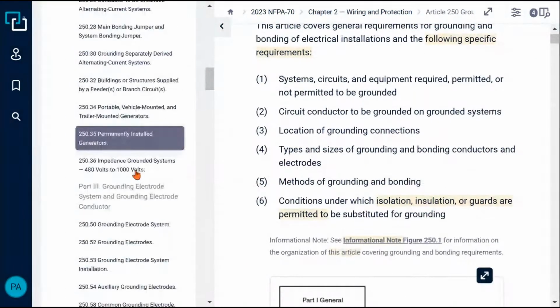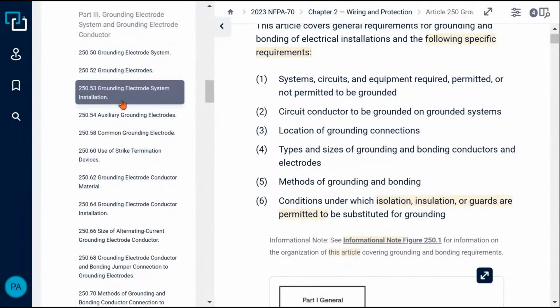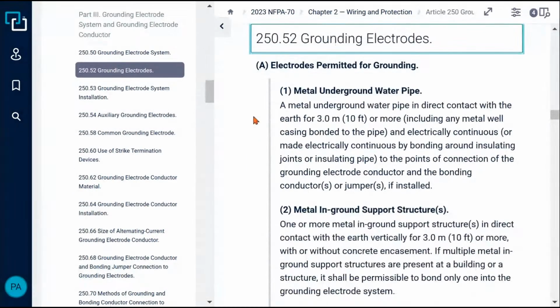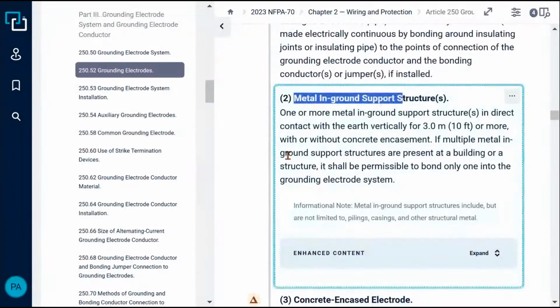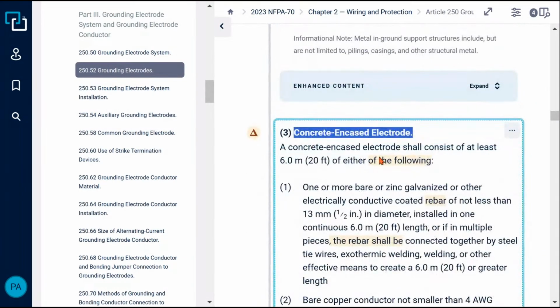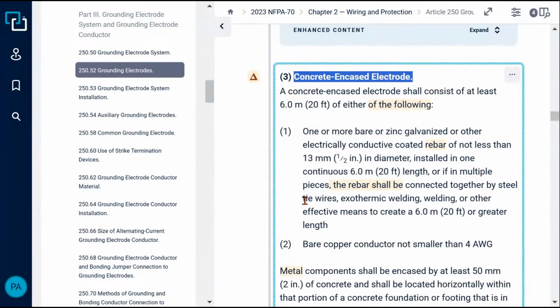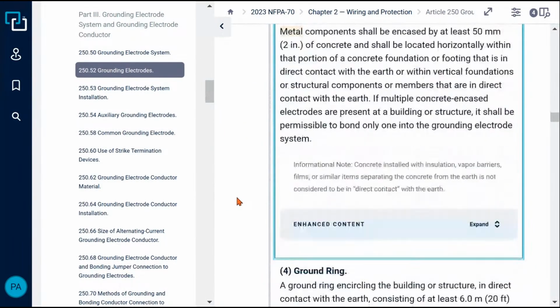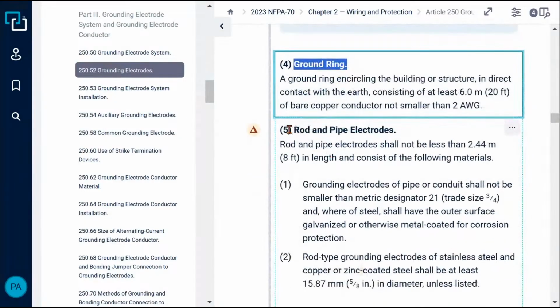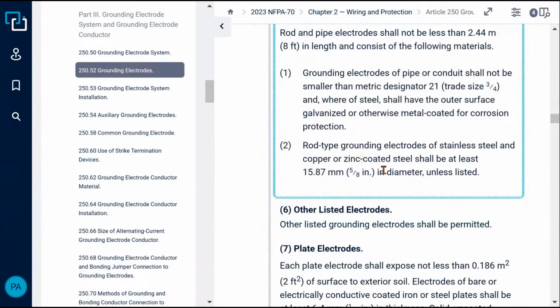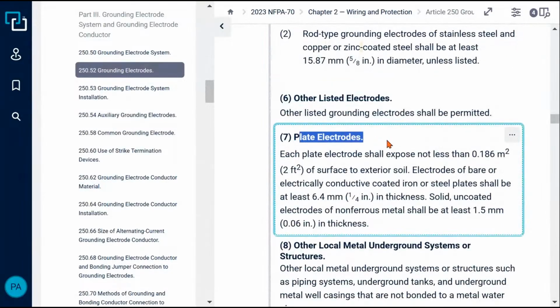People can appreciate that. So remember I was talking about the different types of rods? There's your metal water pipe, your in-ground steel - basically I-beams driven into the earth, encased in concrete, 10 feet or more. There's your concrete encased electrode, which is slang for UFER. There's your ground rings, and your rod, pipe, or plates. There's the lengths, the sizes, and the plate rules and that type of thing.